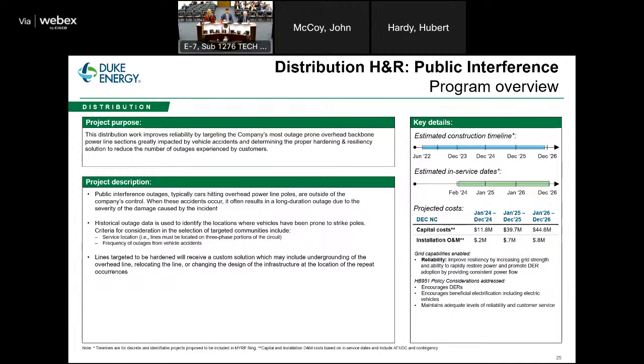This is a data-driven approach, again looking at outage history but focused on specific car-versus-pole cause codes. We focus on three-phase only, where the greater impacts would be, based on the frequency of events seen in those areas. The solutions include a design change, including relocation, possibly undergrounding, to remove the facilities or move them out of the impact zone for previous accidents.